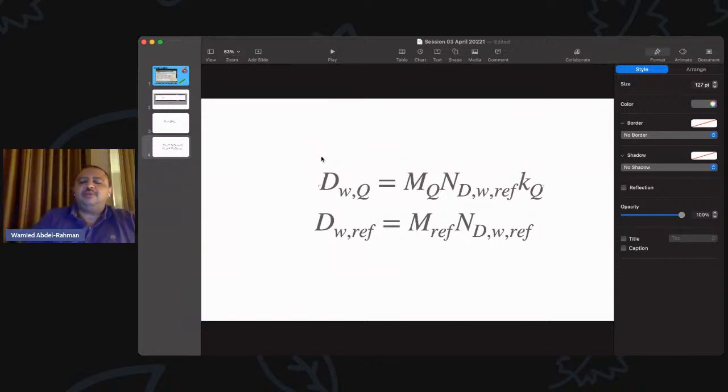One thing you have to be careful with is that in practice, you could actually claim that if you can measure these quantities, you don't need Monte Carlo, and that is true. So if, for example, in a standards lab, you can measure the dose accurately for a particular beam, then you just put the chamber. You have a dose in water for cobalt and dose for that beam. Take the charges, and using this equation you can calculate.